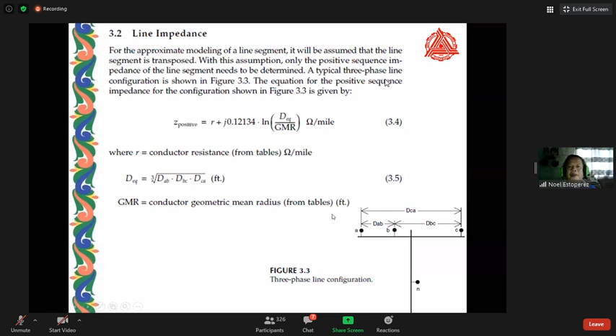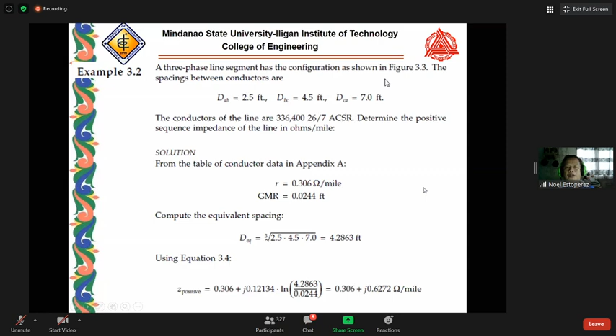In this case, we have an example with 2.5 feet spacing, and 4.5 feet horizontal space. So this is DCA, which is 7. The conductors are 336,400 ACSR. Finding the positive sequence impedance, we will get 0.306 + j0.6272 ohms per mile.